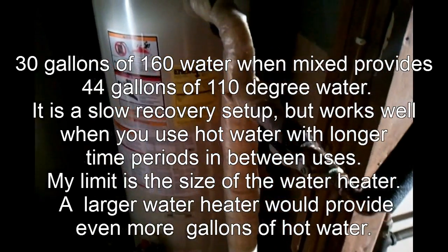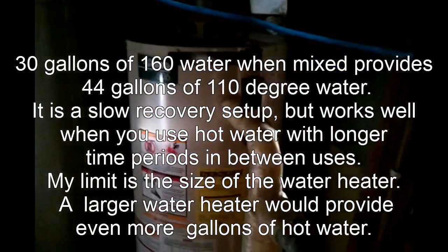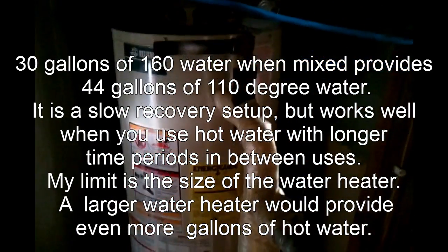Something I forgot to mention here is before it comes up to this water to air heat exchanger, it goes through a tube and tube heat exchanger that I made here, so that 160 degree water from the corn stove heats the water in the 30-gallon water heater just through natural thermal siphoning. So if I run this when I get up in the morning, I have a tank of 160 degree water, and obviously that's not a safe temperature to send upstairs, so there's a mixing valve hooked up before it goes upstairs, so the hot mixes with the cold, so it's sending 110 or 115 degree water upstairs.